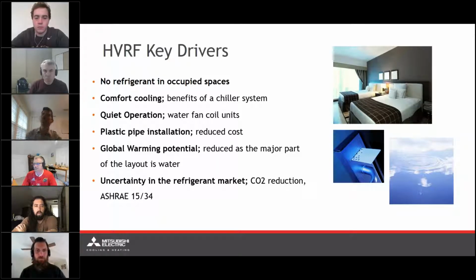And lastly, and this can't be understated, the uncertainty of the future of the refrigerant market. We are all collectively benefiting from the fact that the VRF market is standardized around an R410A refrigerant for this particular generation. But over the next few years, no one can really say definitively what direction all manufacturers or individual manufacturers are going to go. I could provide some insight into where Mitsubishi is looking, but every 6 months I hear an update that could potentially change that. So we're not even certain we're standardizing around any individual refrigerant moving forward. I don't know if it's going to be R32, a blend of some sort, or if everyone goes in different directions.